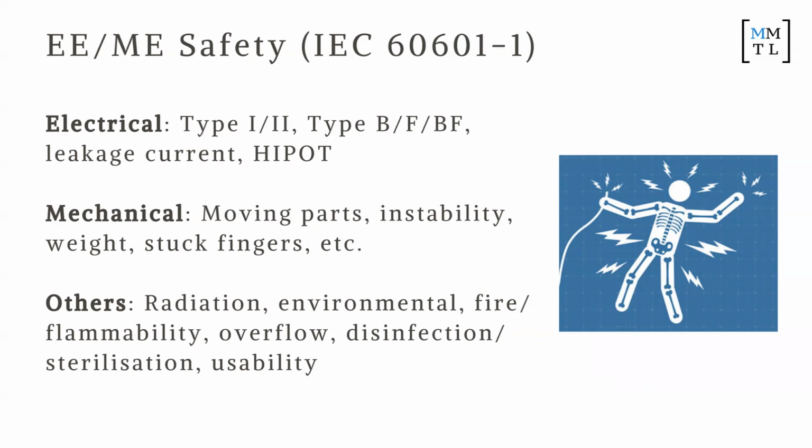So this is again for bigger devices like MRIs, CTs, that you're not going to accidentally kill someone with a moving part, that there's not going to be some instability, like a component just sort of falls off, right? Things like heavy weight or stuck fingers. And then there's a couple of other things as well. You need to demonstrate that, for example, your device is not going to catch on fire, right? There's not going to be sterilization issues or any usability issues as well.